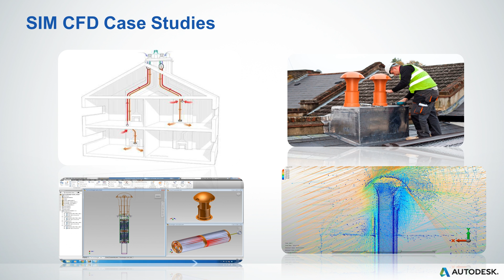to minimise the pressure drop through the tube system and therefore maximise the flow throughput, whilst also achieving the optimum surface area for heat exchange permissible within the manufacturing cost constraints. The net result is a design with 90% efficient heat exchange, so that for a 10-degree differential between inside and outside temperature, the incoming air would only be 1 degree cooler than the air already inside the building.